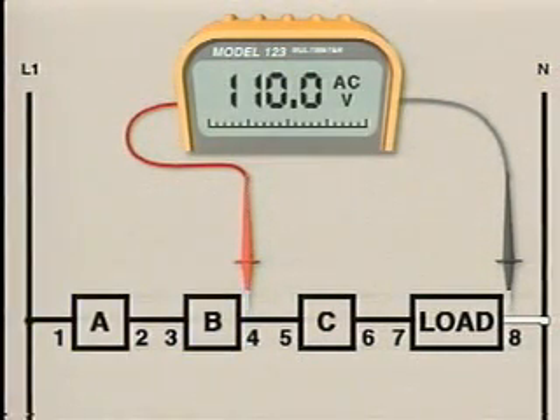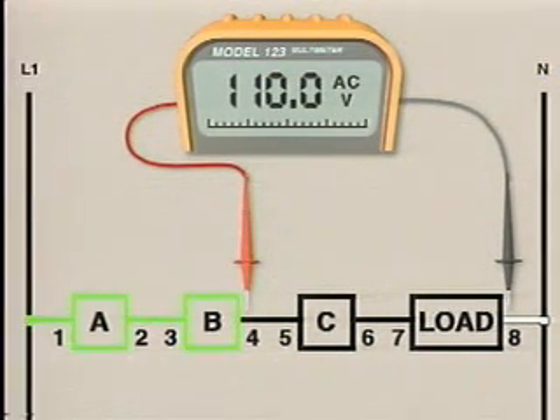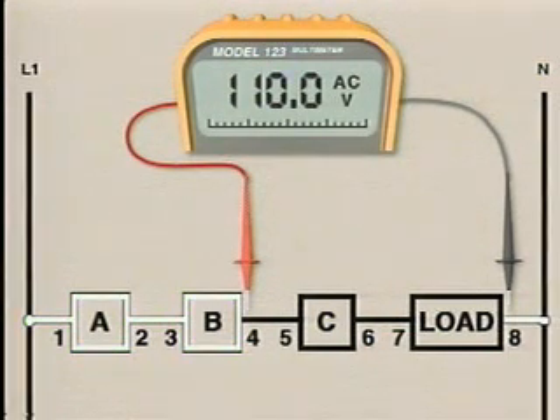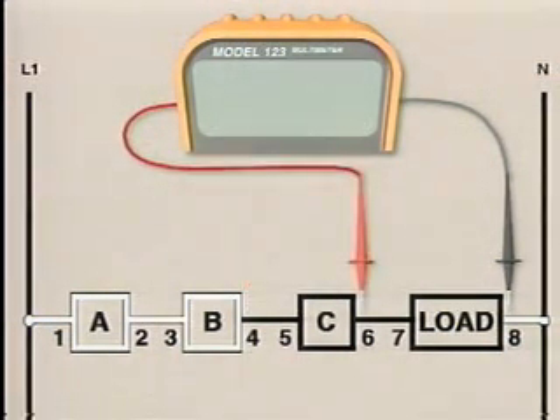The voltmeter indicates full line voltage. By obtaining an indication of full line voltage at test point 4, we know there must be a complete circuit path from L1 to test point 4. This means that none of the components or wires in that path can be causing the problem. The next point to test should split the remaining portion of the circuit in half. So we'll make the next check at test point 6.